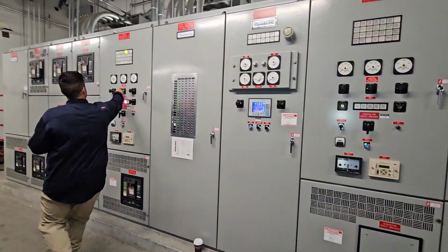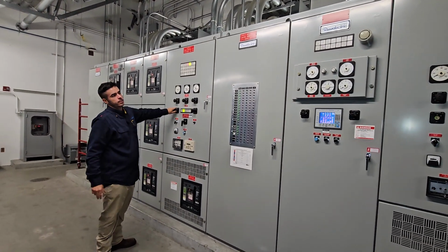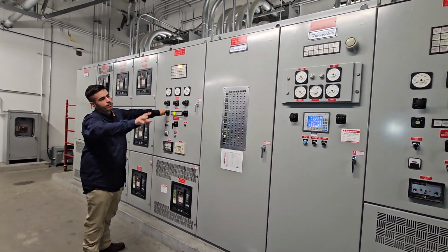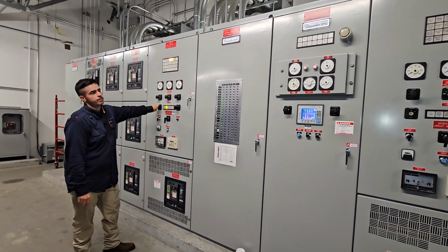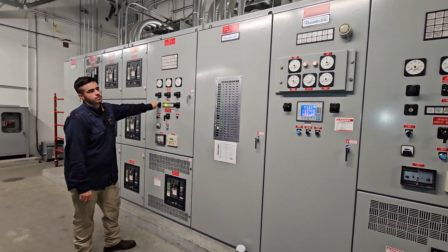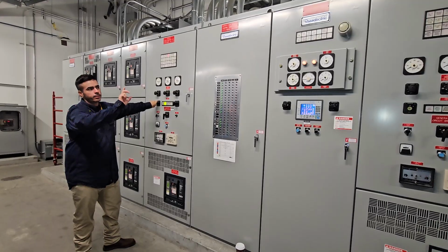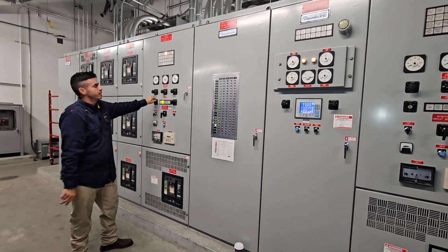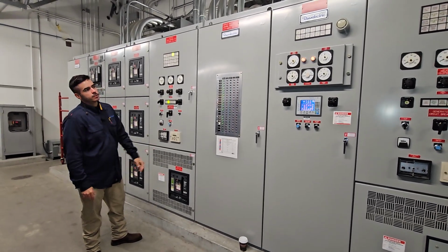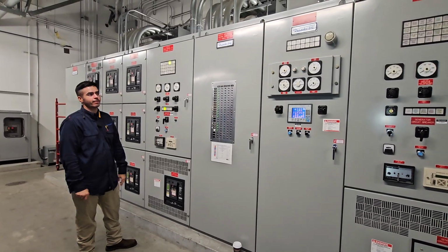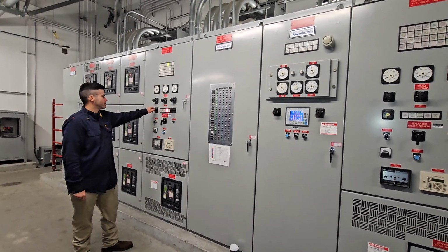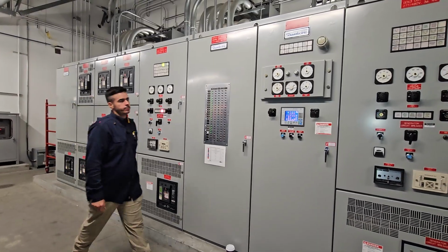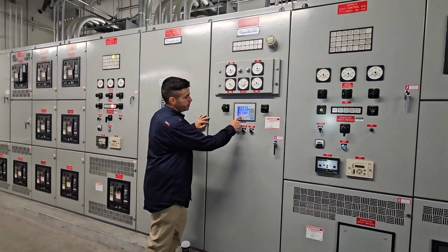I can kick this out of the bus, turn the synchroscope, and I'm going to let it go a little further before I try to bring it back. So right now it's going clockwise, right? But you see how fast it brought it back? Then to end the no-load test, we just press the button again.